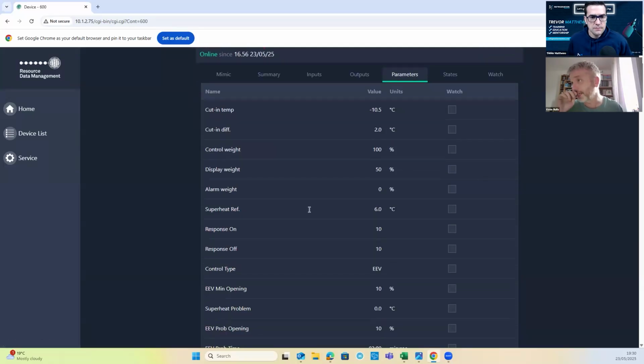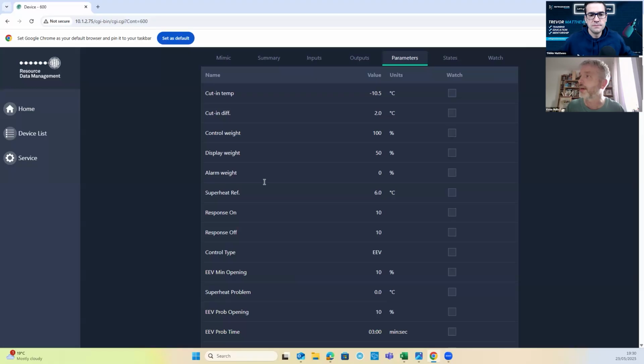Okay, so in our parameters that we're going to do, other than that, alarm weight. You might not want it to alarm on air on or air off. Depends what setup you've got. If it's a cabinet, alarming on the supply air probe is probably right. That's 0%. If it's a cold store, you're going to be more concerned about the return air temperature, sorry. So you can set that to 100%, and that will then alarm when the cold store gets warm rather than the supply air into the cold store getting warm.